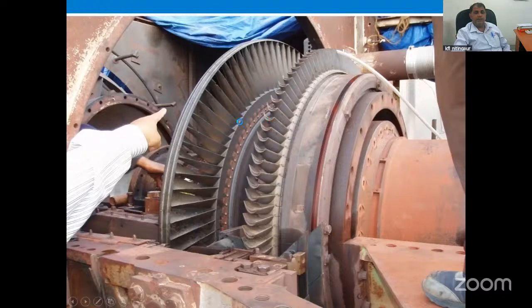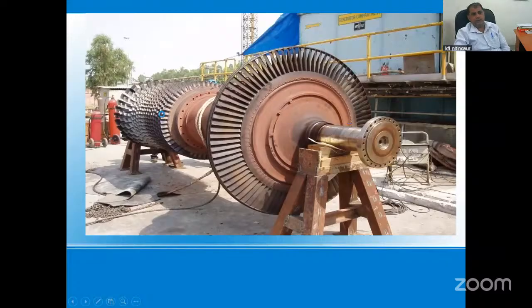Only rotor weights. Rotor means this is the compressor and turbine buckets and its shaft weight. This is the rotor. Its weight is approximately 15 tons. When we put the rotor outside the turbine, all the blades, turbine blades, compressor blades, bearings area surface, coupling area surface, all the rotor is thoroughly checked, and it is for its reliable and sustainable operation.